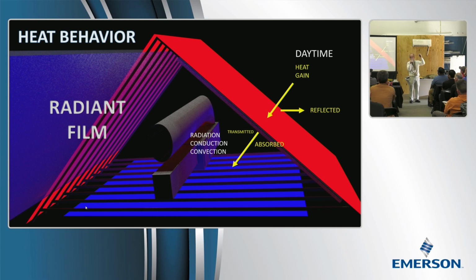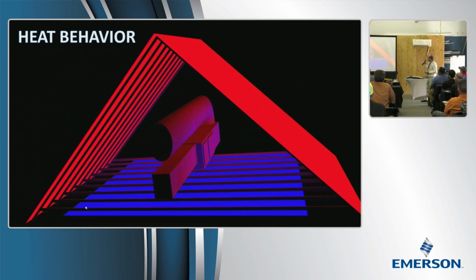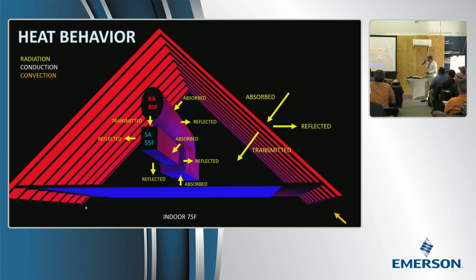If you choose to put in a radiant barrier in Florida, I'm going to say all the way up to Jacksonville, really, I don't know why you wouldn't expect the ducts to sweat. I'm going to predict they're going to sweat, because you're not going to get that radiant heat that kept it from sweating, because the radiant barrier film's not going to let it through. So we're exchanging heat not only through the roof, but the lack of heat between the ceiling and the duct. Obviously, it's going to be a lot cooler down by the ceiling, down by knee walls, and the higher we get up in that space, the less it's going to be.